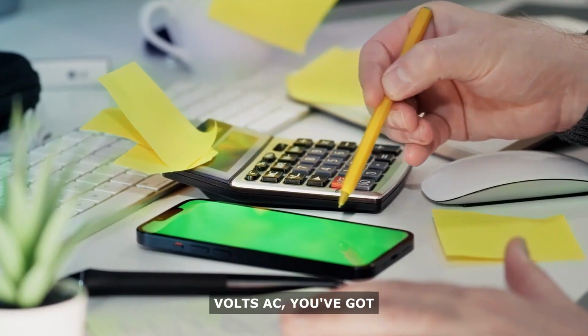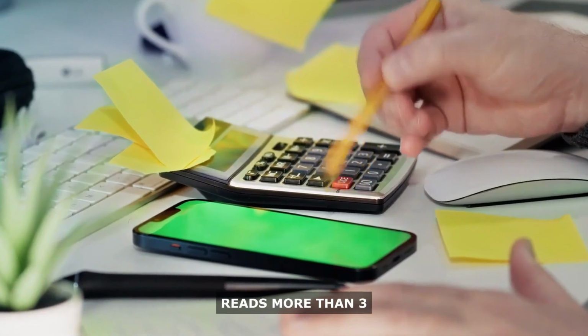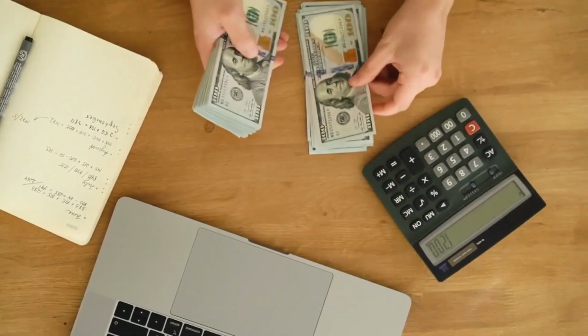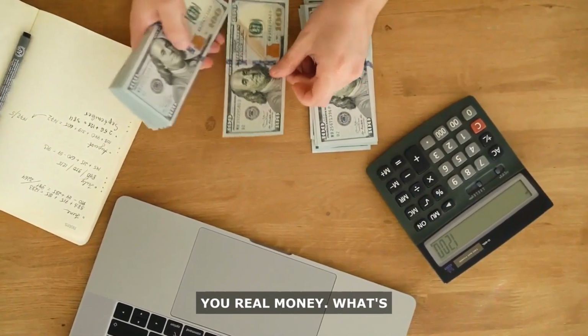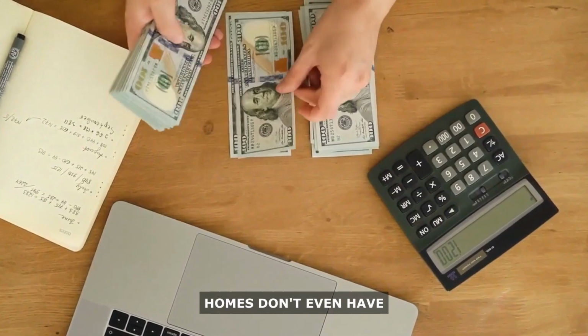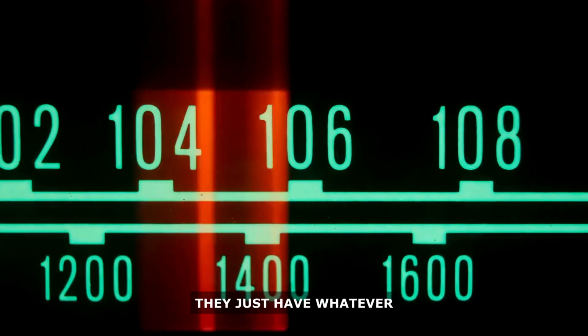You take a standard multimeter, costs about $15, and you measure the voltage between your water pipe and a ground stake in the earth. If it reads more than 0.5 volts AC, you've got stray voltage. If it reads more than 3 volts, you've definitely got a problem that's costing you real money.